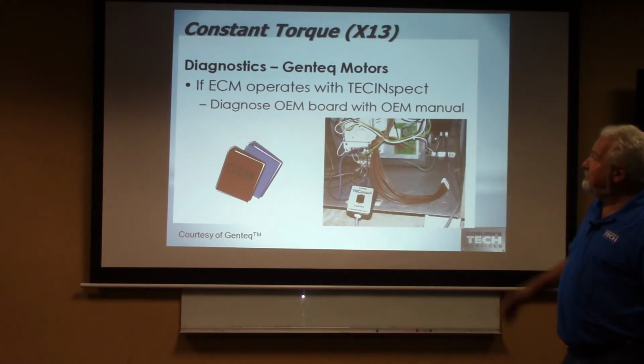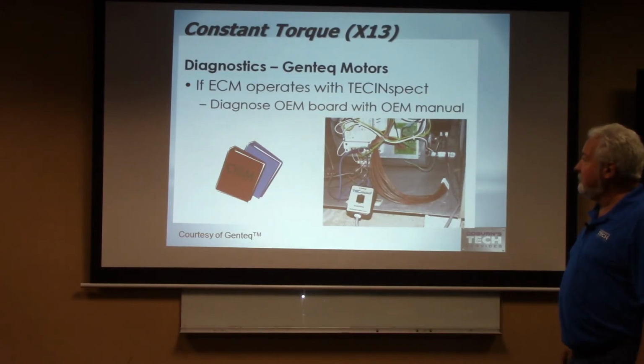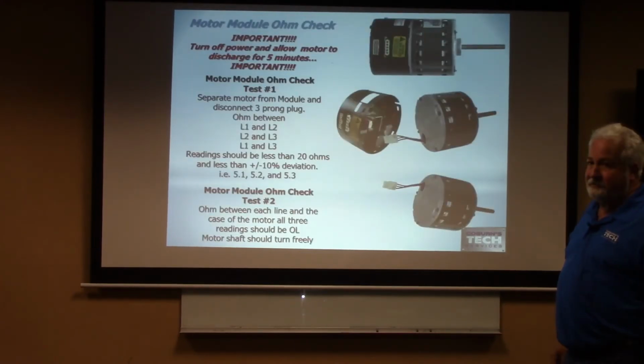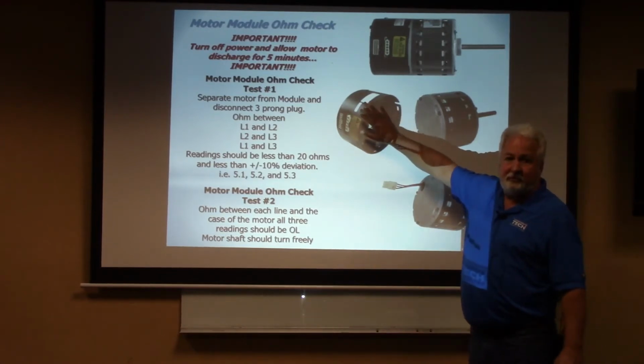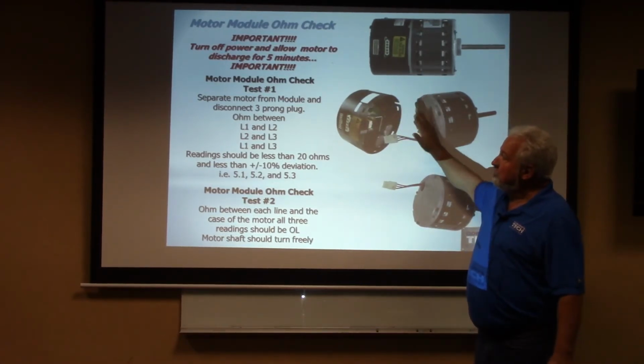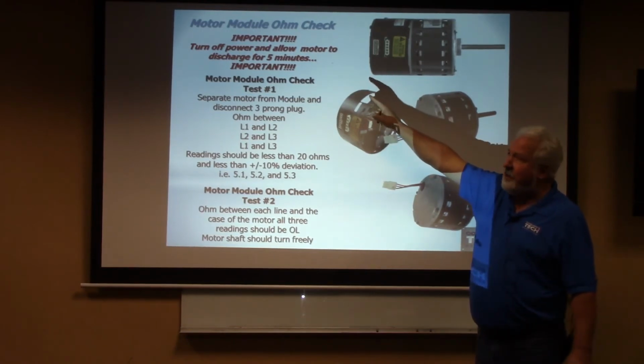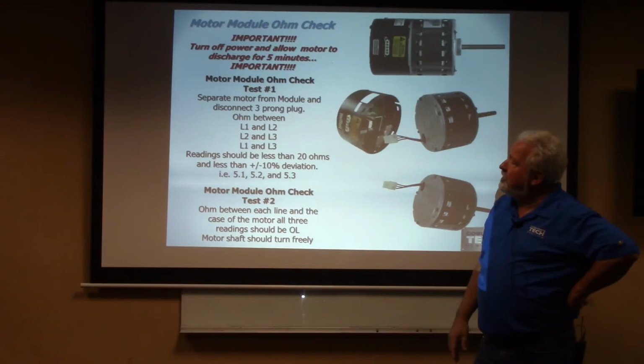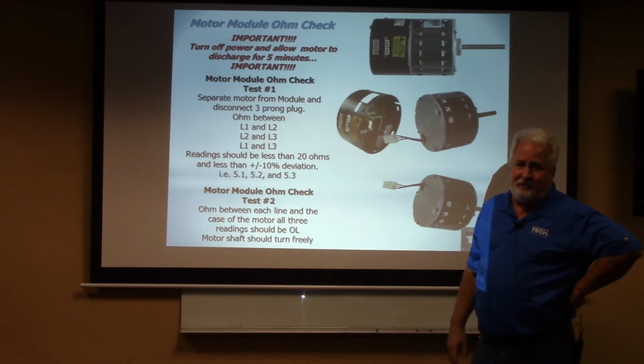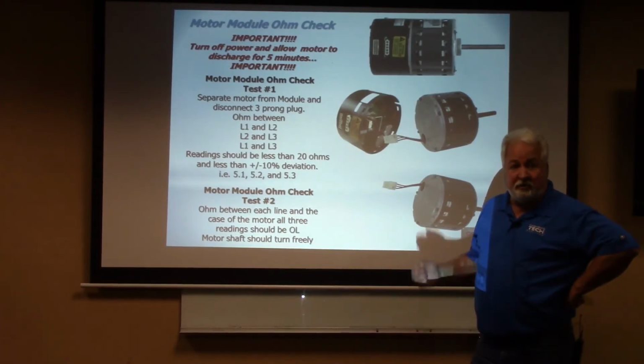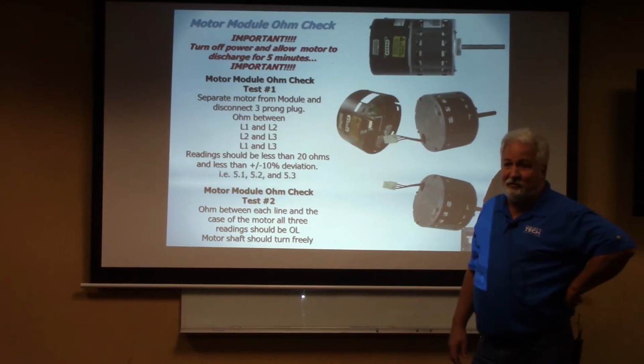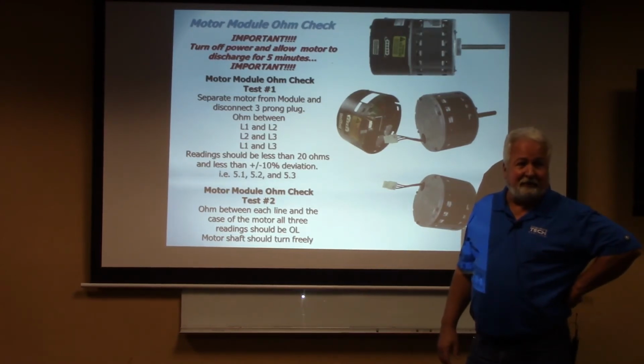If the ECM motor operates with the Tech Inspect motor, diagnose the board, right? We're going to go back to the board, and that's going to be going back to that OEM stuff. If it doesn't, we're going to need to find out, is it the control module or is it the motor itself? So we're going to separate that. But before we do that, it's important for that power to be shut off for 5 minutes. If you don't discharge that motor for 5 minutes, those capacitors will hold a charge. And unless you have your helper doing this for you, it's going to light you up. But it's really kind of fun to watch him do it, okay?